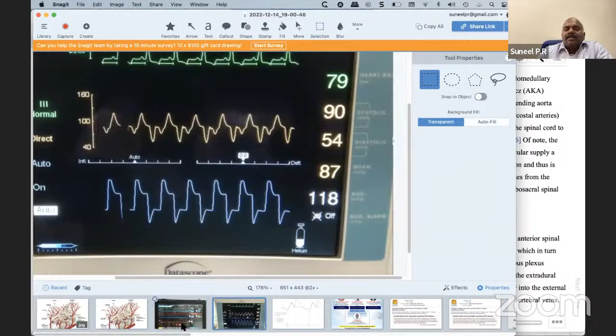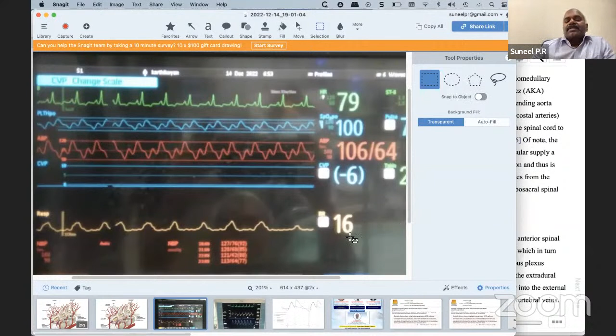Is my cross marker seen? Yes, sir, it is seen. So when you read the arterial pressure tracing, you have to look at the screen of the IABP. 118 is the augmented pressure, which is shown here, and the systolic pressure is 90. When the augmentation is proper, the unaugmented systolic pressure is much less than the augmented diastolic pressure. So the pressure you see as systolic pressure is actually the augmented diastolic pressure. I just wanted to mention this, whether or not it has been understood by the audience. I'm not very sure; I did not make a comparison of the arterial trace with the IABP screen. This is an extremely important point.